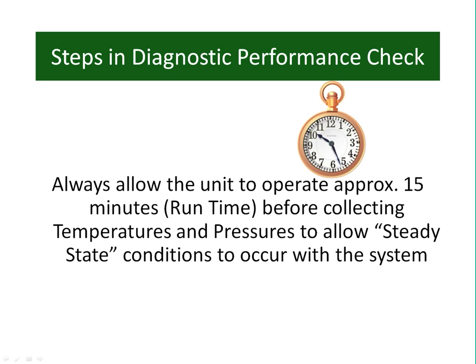So when you're going to approach a unit that's got some kind of issues, the first thing you want to do, in my opinion, is obviously check the filter. And remember, the homeowner changes that filter as you were driving out to the job site. Just go look by the garbage can. You typically find that throw rug, which used to be the filter. But I want you to operate that unit for at least 15 minutes.